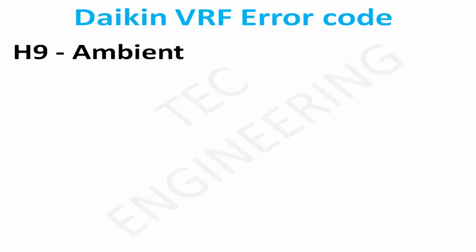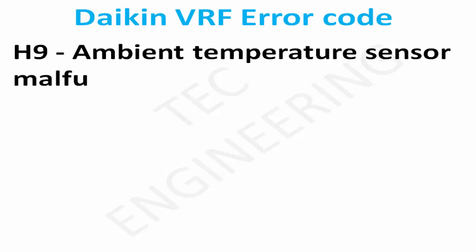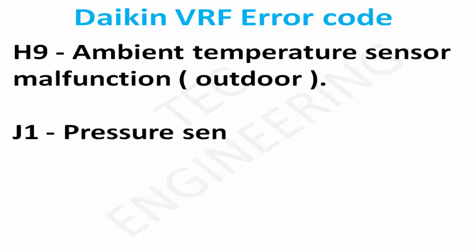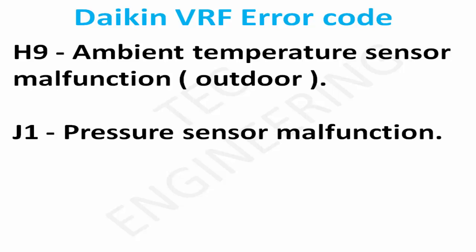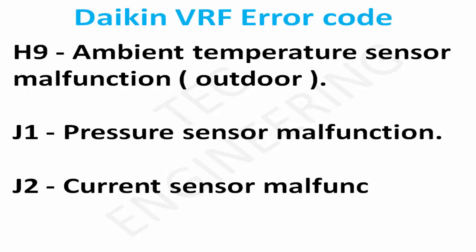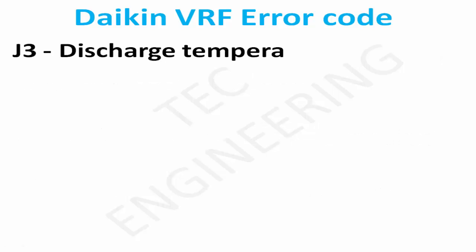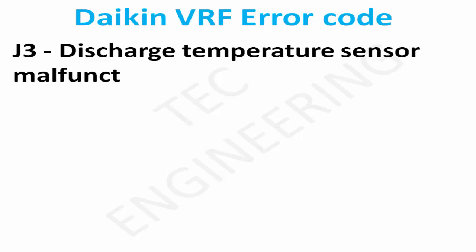H9: Ambient temperature sensor malfunction, outdoor. J1: Pressure sensor malfunction. J2: Current sensor malfunction. J3: Discharge temperature sensor malfunction, outdoor.